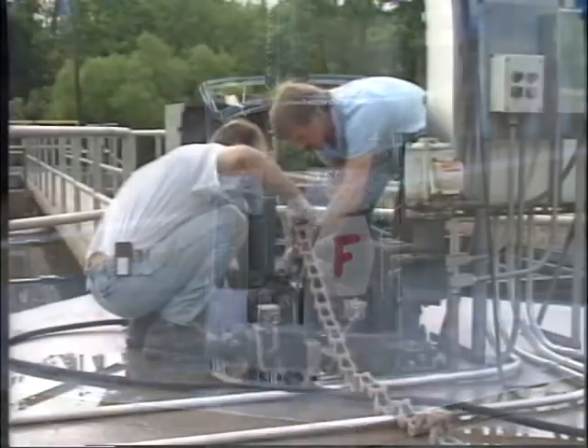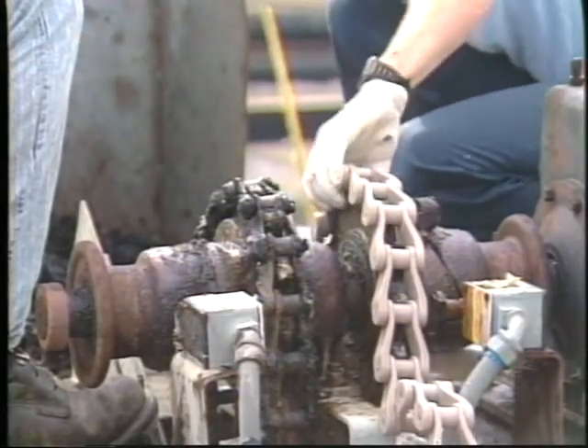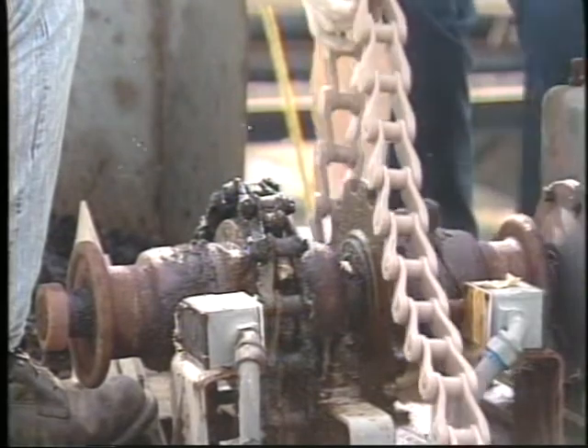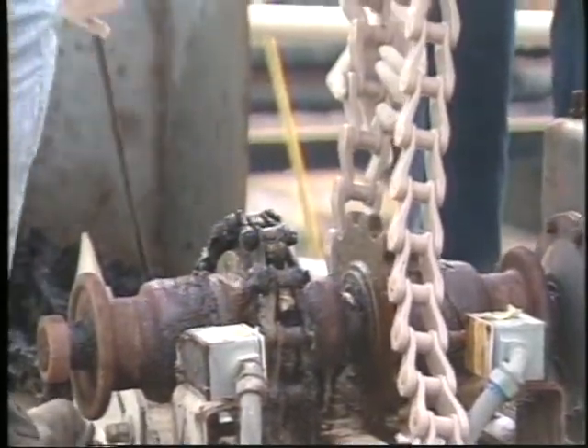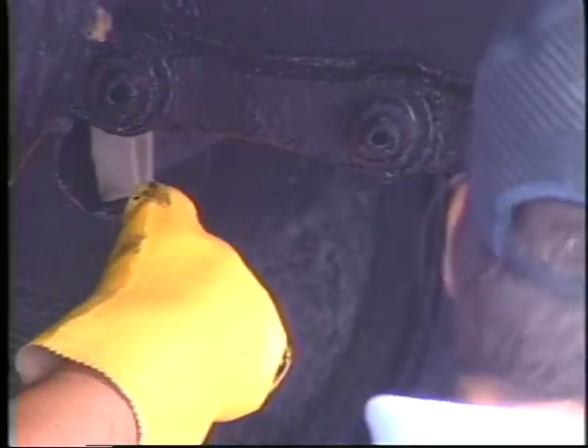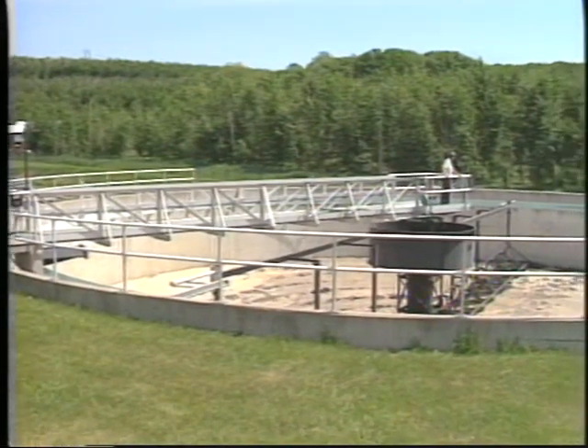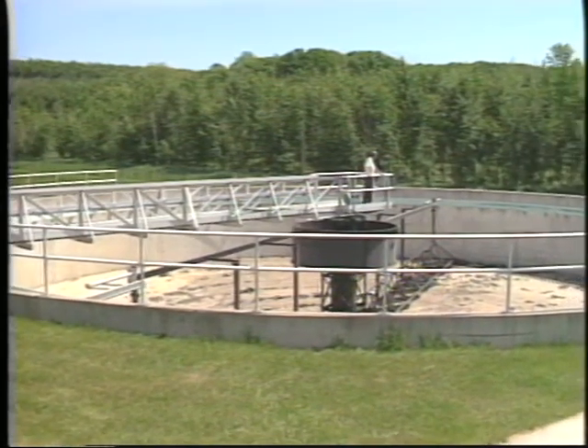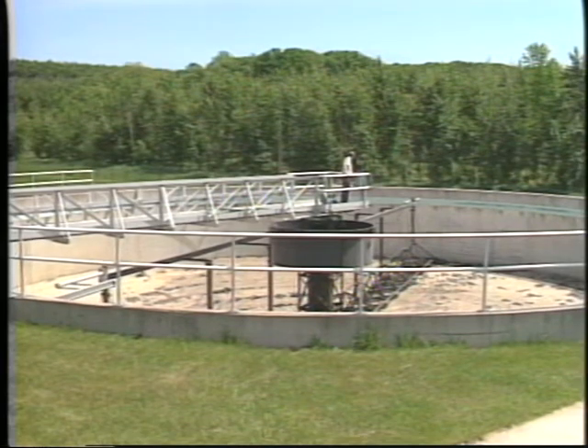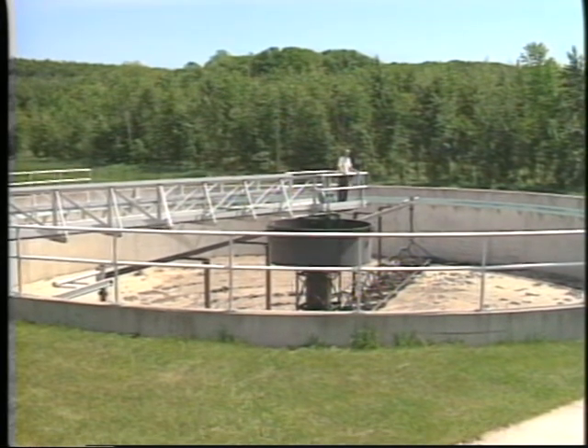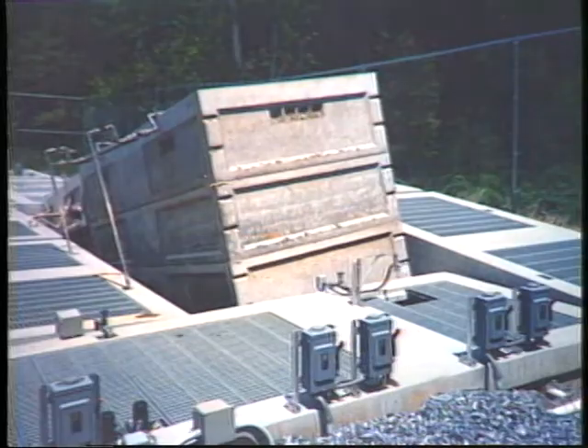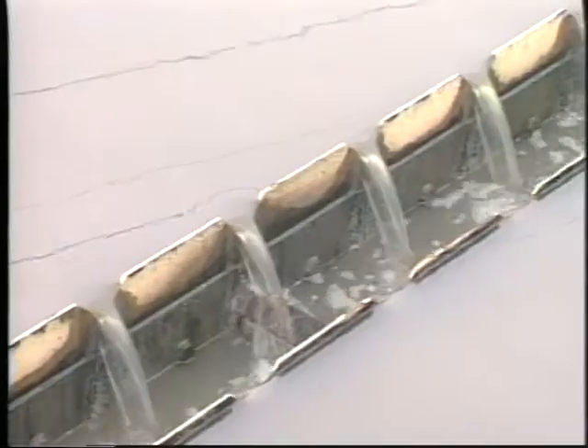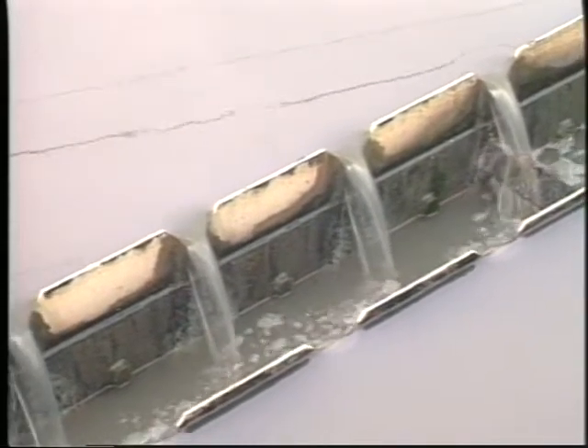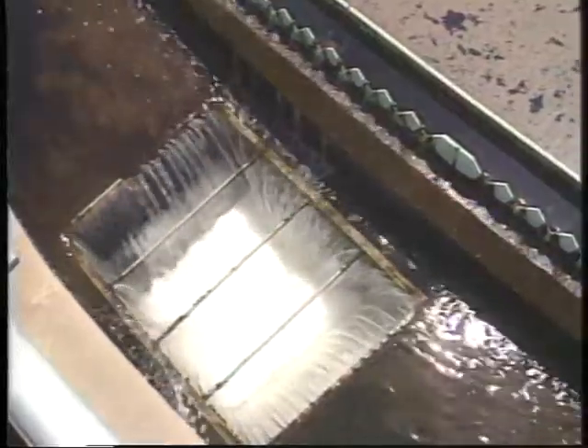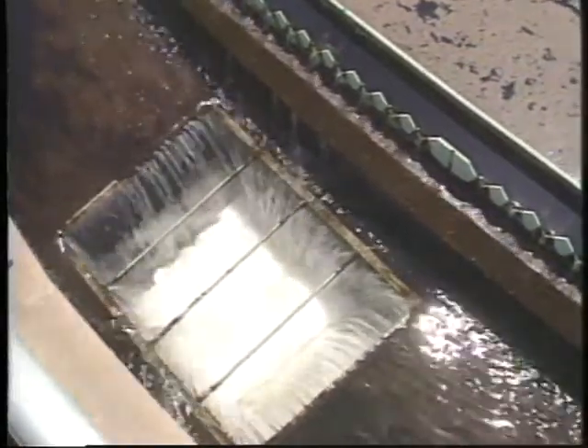Proper maintenance of the clarifiers is also a requirement of the NPDES permit. Please be sure to follow all manufacturers' recommendations for lubrication, inspections, and adjustment of clarifier components. Clarifiers must also be periodically dewatered or drained in order to inspect and adjust drive units and to inspect the tank structure and remove debris. Care needs to be taken when dewatering any tank because a high water table can cause tanks to float right out of the ground. And now, only after the wastewater has been carefully and properly processed in the clarifier, can it be discharged onto the next stage of treatment at the wastewater treatment plant.